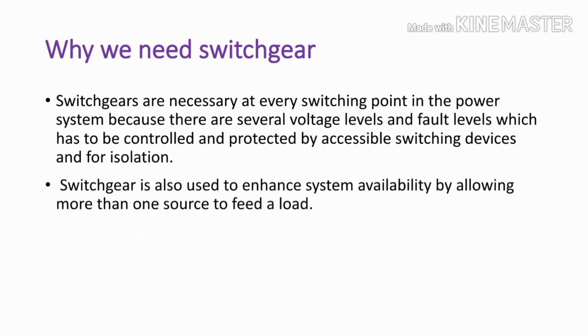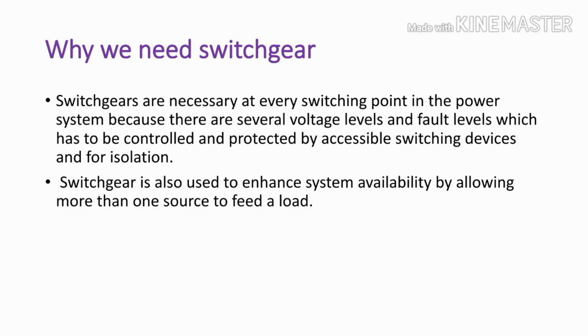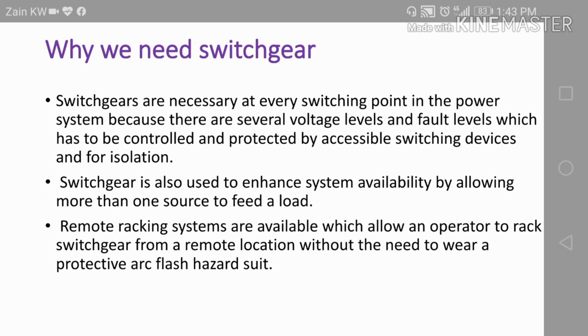Second, switchgear is also used to enhance system availability by allowing more than one source to feed the load. With normal switches you can connect only one incoming source to one output, but with switchgear — being a combination of a group of feeders — you can connect two incoming sources to one motor feeder. If incoming source A fails, you can run that motor with incoming source B. That is another advantage of switchgear.